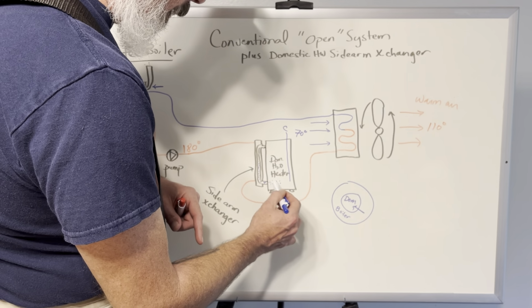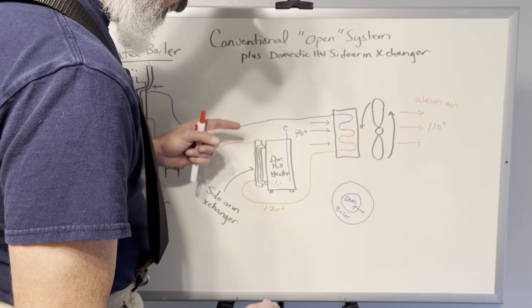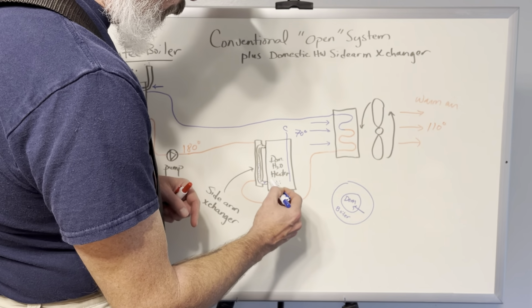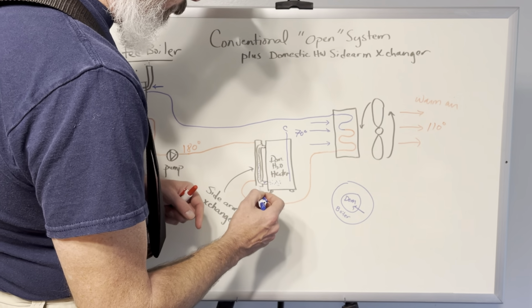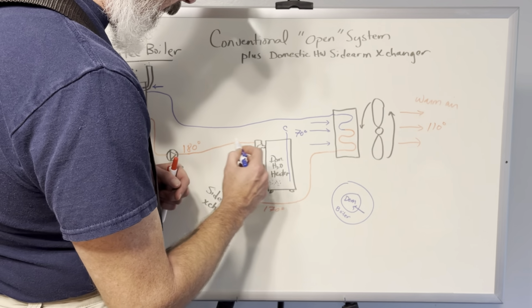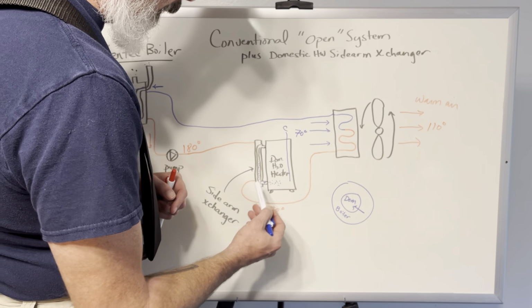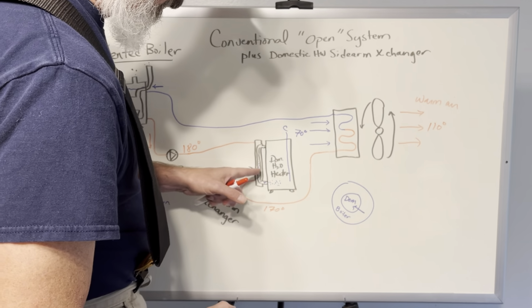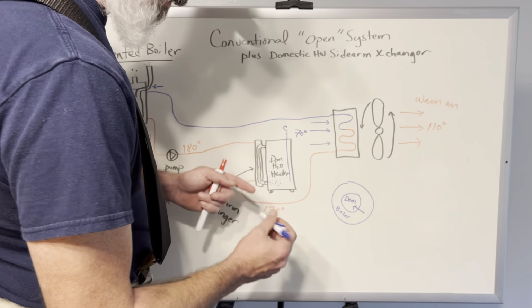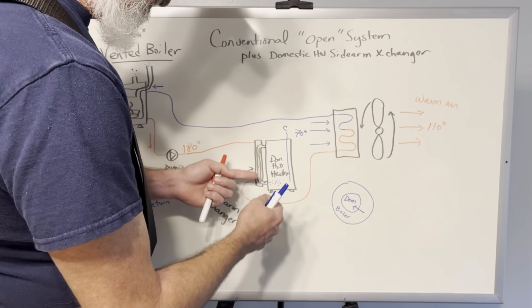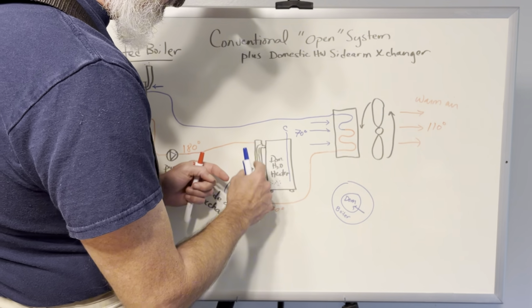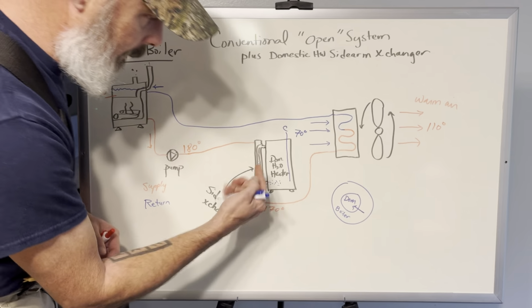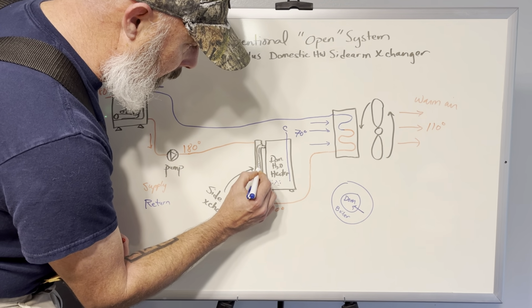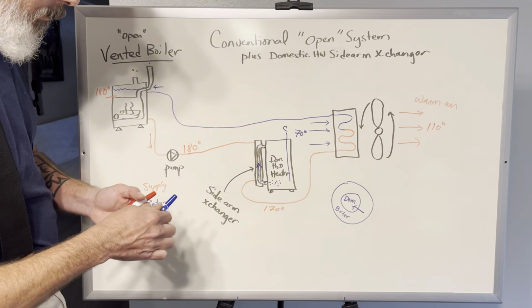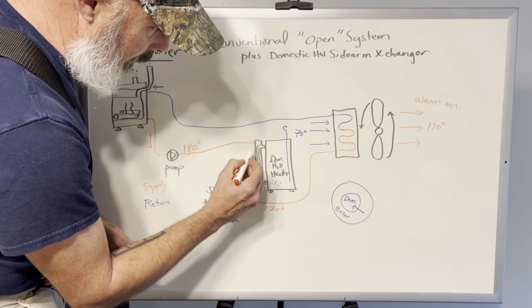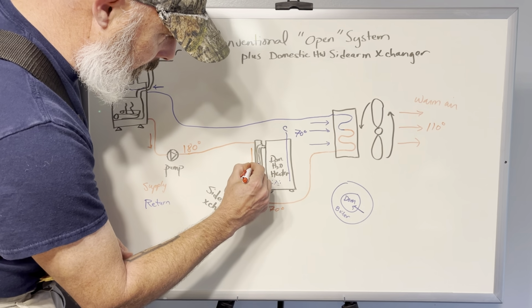So this water is cold, and it's going to move in this direction. As it gets warmer, this 180 degree water in the jacket going around is going to heat this water up, and that's going to want to rise because it's becoming less dense the hotter it's getting. So it will start to rise and go up. So the water from the water heater side is going up, while the water from the boiler side is, in this situation, going down.